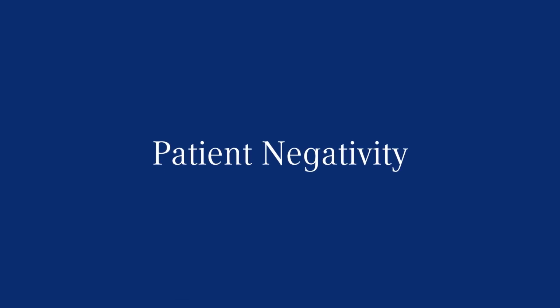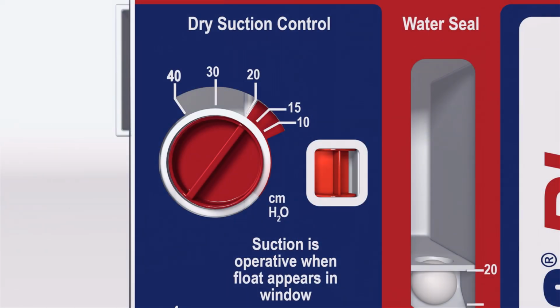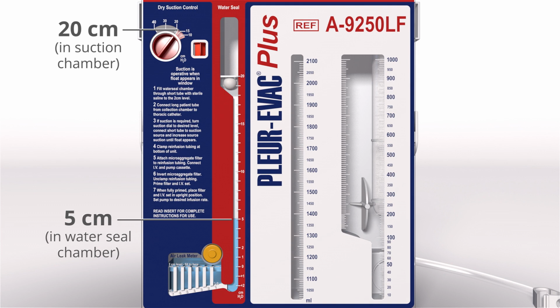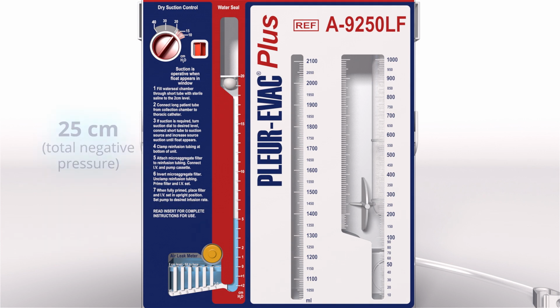Patient negativity can be determined by adding the level of imposed suction to the number corresponding with the water level in the water seal. For example, 20 centimeters of water dialed in the suction chamber is added to 5 centimeters of the height of water in the small arm of the water seal chamber. This equals 25 centimeters of water, or the total amount of negative pressure in the patient's chest cavity.